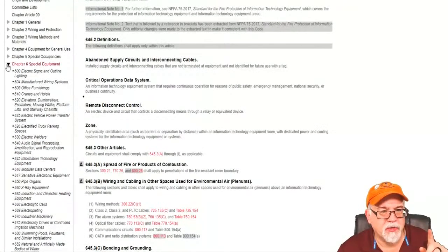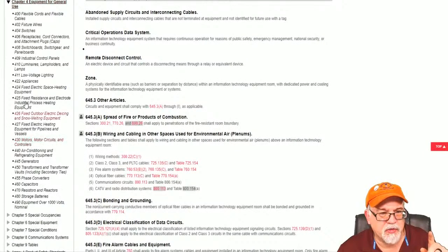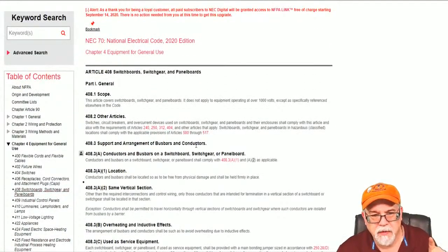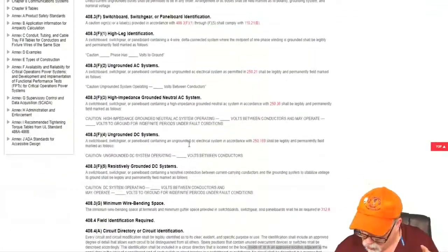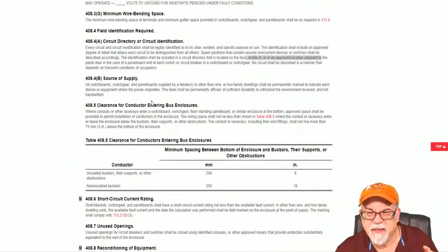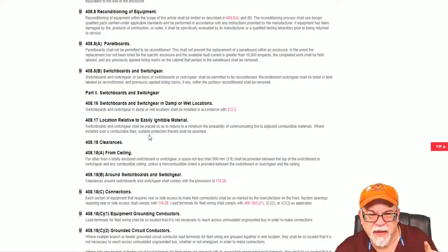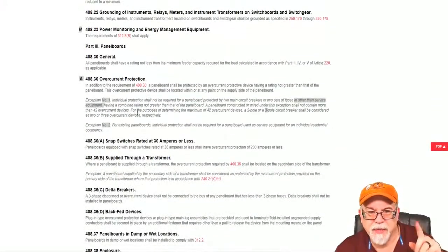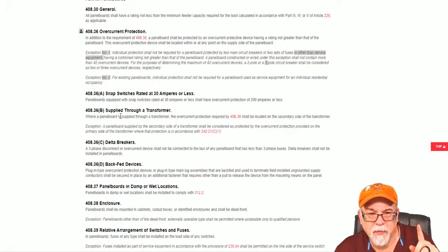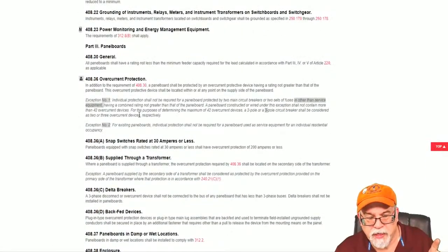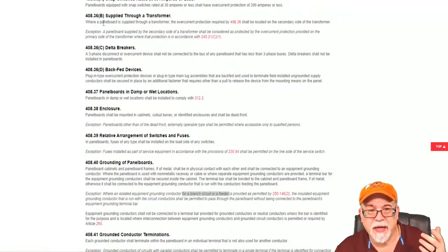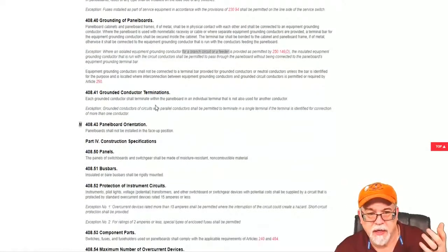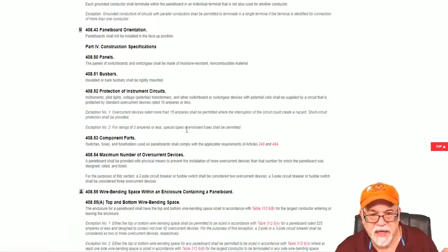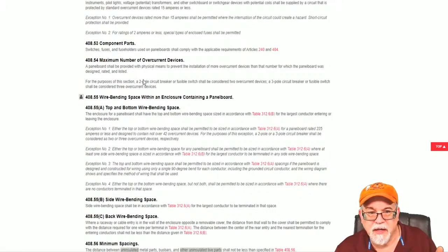Now, before I even go to 230, I will say what's interesting is I will go to 408. And if you go to 408, I wrote down one of the aspects. Hold on here, let me find where. Here we are in actual part 3 of 408. Gives you a lot of information here. It talks about panel backfed, delta breakers and all that good stuff. It goes on panelboard orientation and everything like that, number of overcurrent devices, everything that's rated for here.